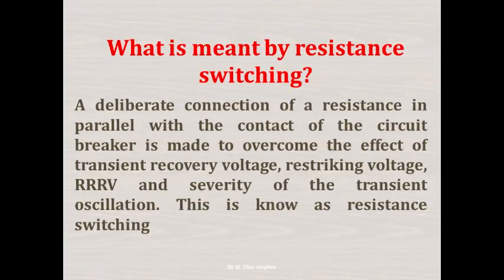What is meant by resistance switching? A deliberate connection of a resistance in parallel with the contact of the circuit breaker is made to overcome the effect of transient recovery voltage, restriking voltage, RRRV, and the severity of transient oscillation. This is known as resistance switching.